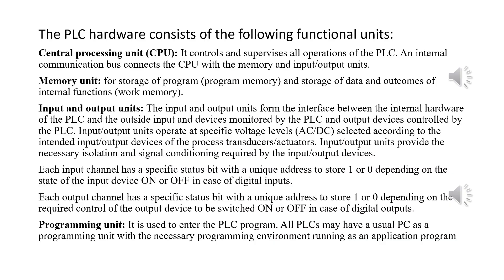The central processing unit is responsible for controlling and supervising all the operations of the PLC, and it is connected to the other parts of the PLC through a communication bus. The memory unit for storage of the program is called program memory, and for storage of data and outcomes of internal functions during program execution, it is called work memory. The input and output units are the modules that provide the required interface between the internal hardware of the PLC and the outside world of input and output devices.